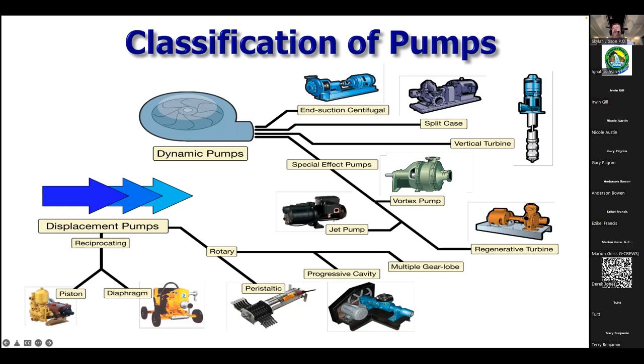Our closed coupled options have no coupler in play. The split case pump is very common in clean water applications. Split case pumps do not like high solids — that has to do with the type of impeller in them. They are very efficient pumps, but do have their own wearables that need attention from a maintenance perspective. Split case pumps are also the most commonly used pumps on fire trucks.